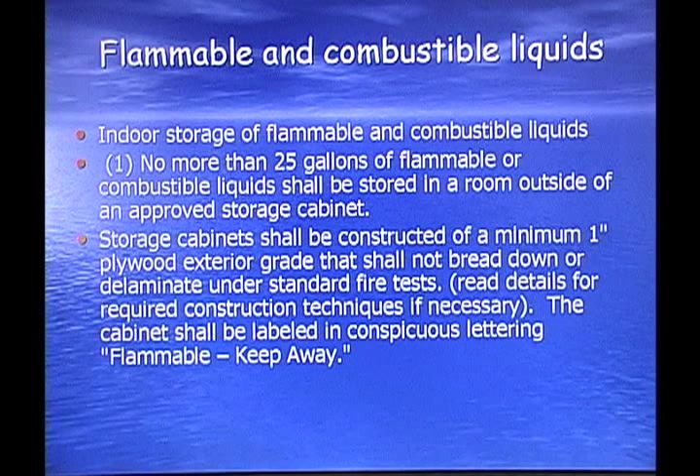Flammable and combustible liquids — indoor storage: no more than 25 gallons of flammable or combustible liquids shall be stored in a room outside of an approved storage cabinet. Storage cabinets shall be constructed of a minimum of 1-inch exterior-grade plywood that shall not break down or delaminate under standard fire test.